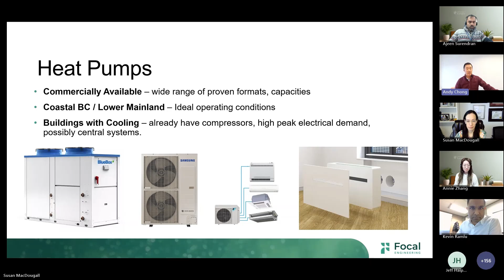In buildings where cooling was already being provided, if we weren't already looking at those as obvious candidates for heat pump heating, we've done something terribly wrong. A building with a chiller already has a massive electric driven compressor, already has distributed maintenance, already has a central plant. To not make that compressor a reversible one that can also do heating is a lost opportunity. Very often in commercial buildings, it's actually the peak cooling that's driving our service size, not heating, because our building envelopes are getting so good. If we already have chiller systems, we should be looking at applying reversible heat pumps.